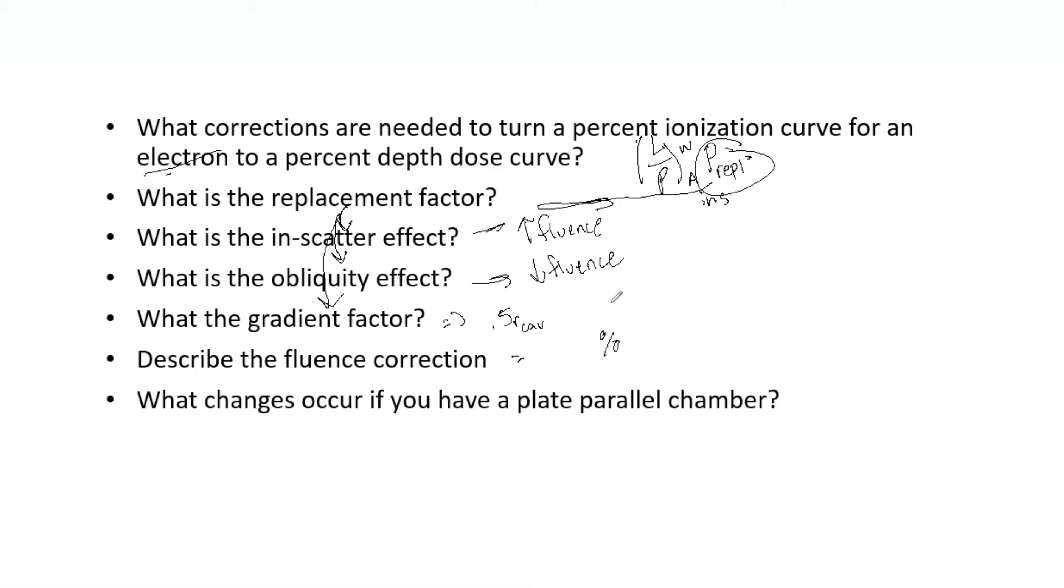And then finally, what if you have a parallel plate chamber? Depending on if you have low energy electrons, you are supposed to use the parallel plate chamber. The P fluence and the P gradient can be ignored for parallel plate. However, your L over rho, that needs to be applied. That one you do in fact need regardless of what chamber you are using. Also an importance is that your effective point of measurement is on the front surface of your chamber.